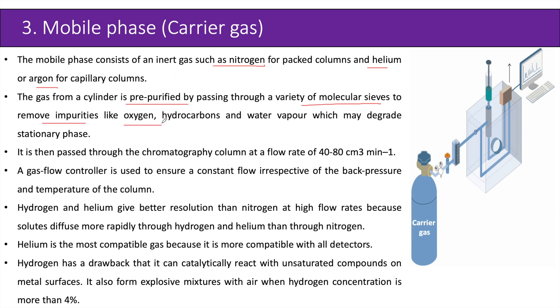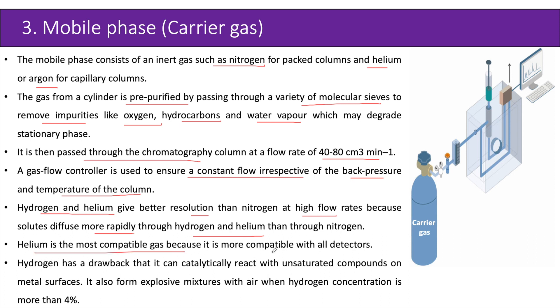The purified gas is then passed through the chromatography column at a flow rate of 40 to 80 cubic centimeters per minute. A gas flow controller ensures constant flow irrespective of back pressure and column temperature. Hydrogen and helium give better resolution than nitrogen at high flow rates because solutes diffuse more rapidly through them. Helium is the most compatible gas as it works with all detectors. Hydrogen has a drawback in that it can catalytically react with unsaturated compounds on metal surfaces and forms explosive mixtures with air when hydrogen concentration exceeds four percent.